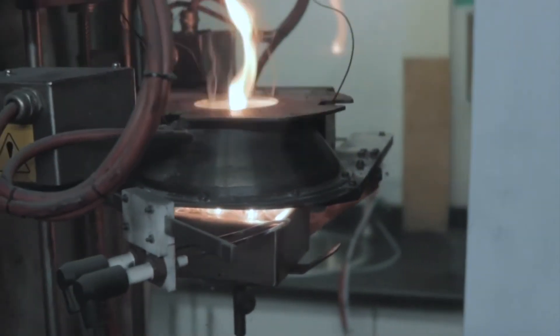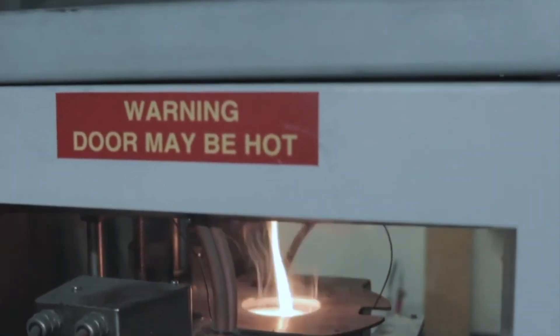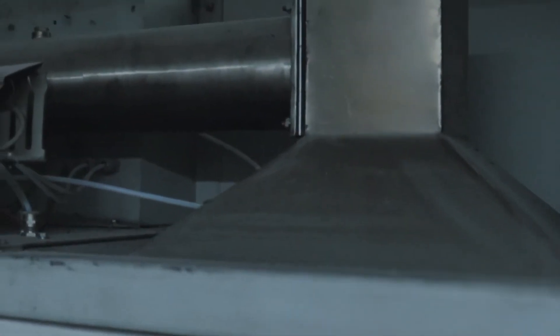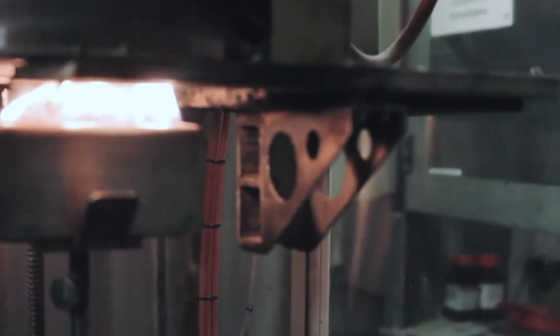Throughout the test, the products of combustion are extracted through the exhaust duct. Within this duct, sophisticated measuring systems are fitted. Data from a light system, gas analyzers, pressure transducers, and thermocouples are used to determine the heat release rate and smoke production from the material.